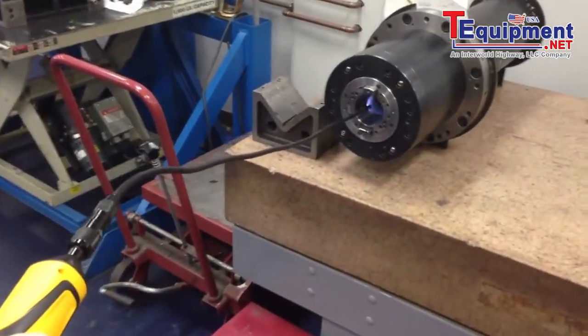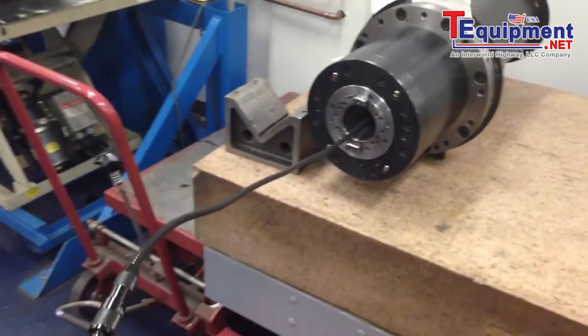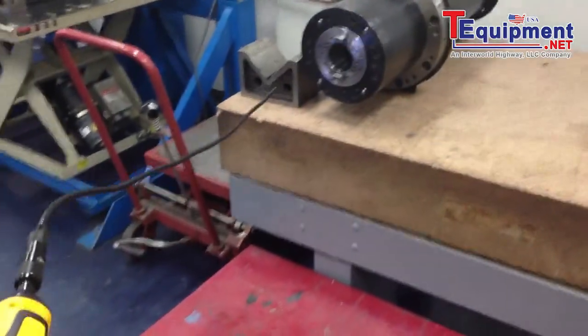Here we have the borescope going inside a spindle, and you can see here live video on the iPad itself. I'm doing live capture of that — both recording it and viewing it simultaneously. It's a pretty cool piece of technology available on the iPad.